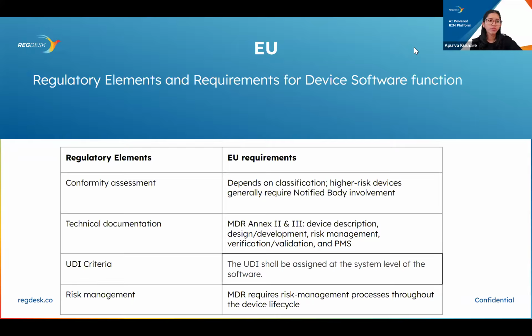So now, in terms of UDI, the software identification shall be considered to be part of the manufacturing control mechanism and shall be displayed in the UDI-PI. The minor software revisions shall require a new UDI-PI and not a UDI-DI. So just to keep that in mind. Also, manufacturers shall ensure the safety and performance throughout the life cycle of the software, through a continuous process of clinical and/or performance evaluation, including risk management. So these are some key elements to take into consideration.